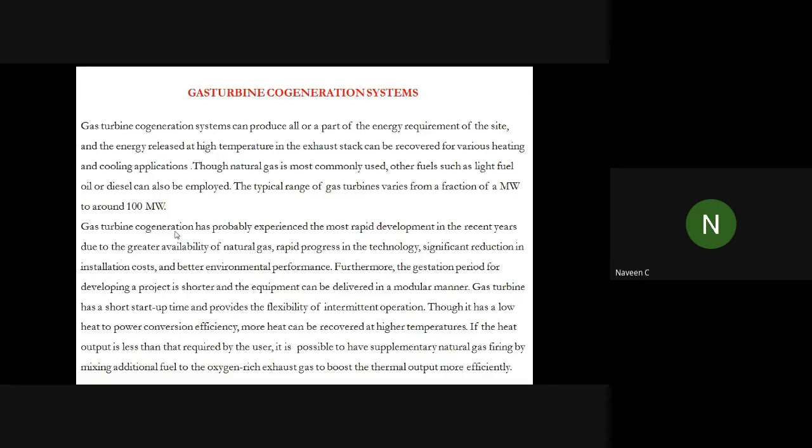The other thing is, if you see the graph of 24 hours in a day for a city, in one particular hour you'll have a peak requirement. Generally a power plant can generate 40 megawatt-hours, but in that hour it needs to produce 50 megawatt-hours. It is not advisable to increase output over a short period using a fossil-fuel-based traditional power plant. So only for that one hour we will use a gas-based turbine.